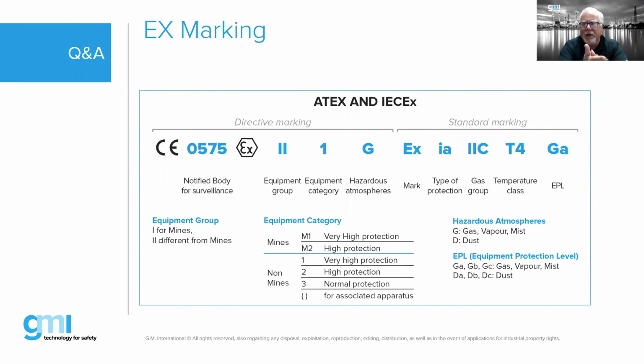And then we have G, which is for gas atmospheres. Then we get into our EX marking. So our EX is telling you it has some sort of explosion protection. IA in this case is intrinsic safety, suitable for zone 0. 2C is good for all gas groups. That's telling us that it's good for every gas group. 2C gases are acetylene and hydrogen. T4 is our temperature code associated with it.